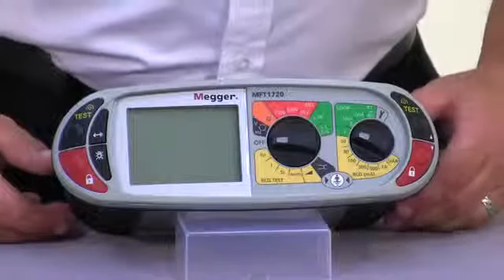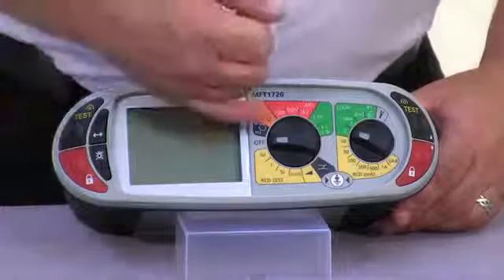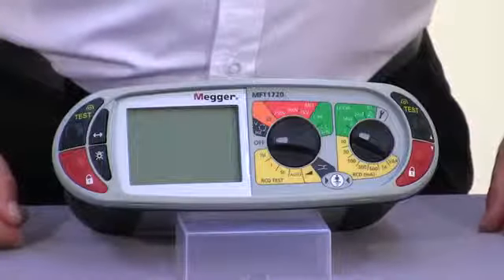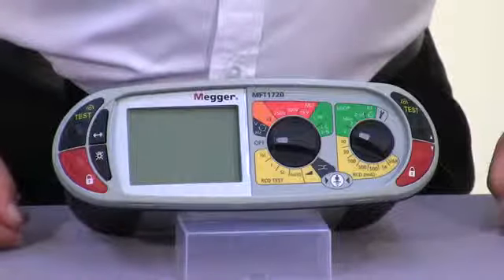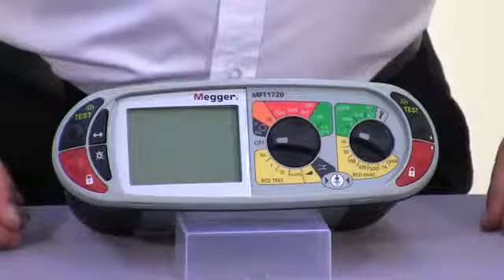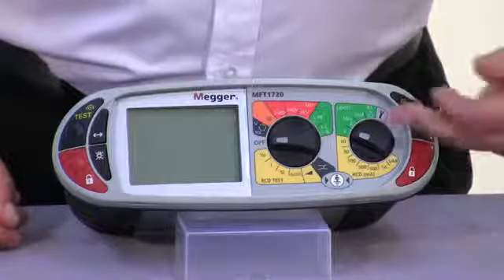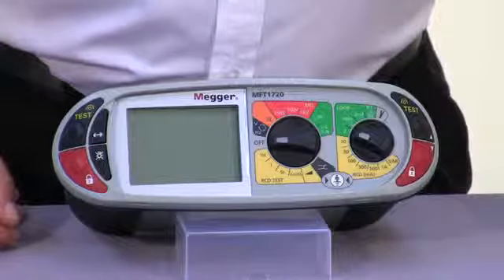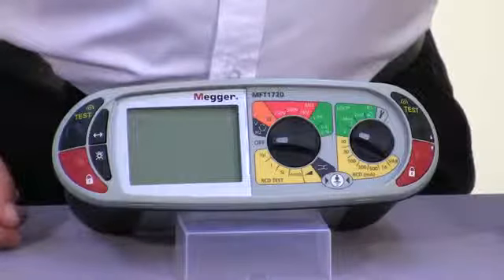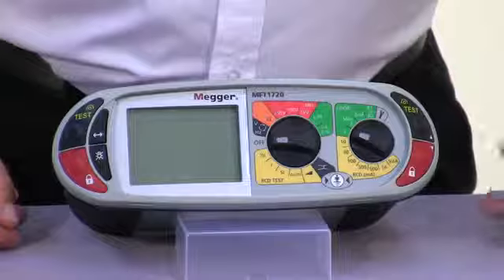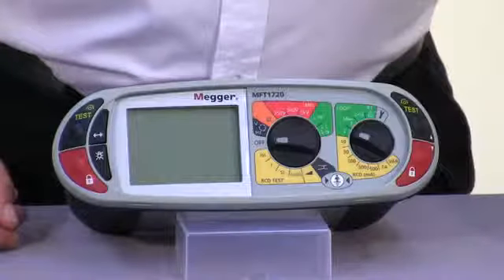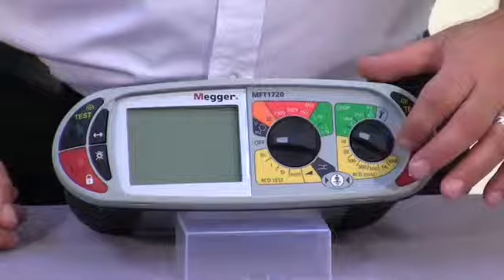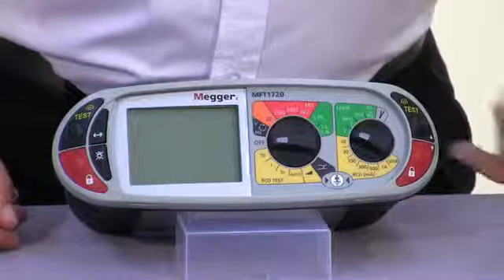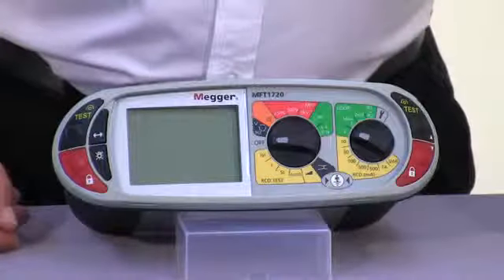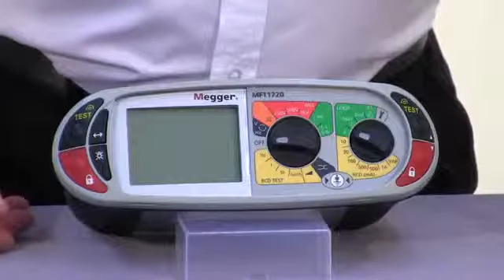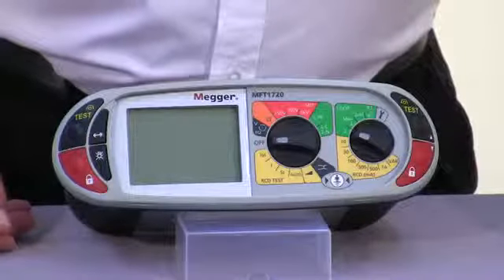Moving on to the MFT1720, we now have incorporated a full phase rotation meter. On the insulation range we've added the 1 kV test facility, and on the loop impedance range there's some additional features, namely the Zmax facility and a calculated R1, R2. The RCD tester now incorporates an auto RCD function as well as the facility for testing variable RCDs. The CT input using the optional CT will allow you to take either measurements for diversity or for earth leakage measurement.